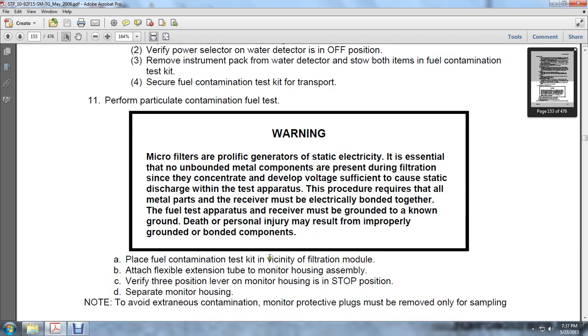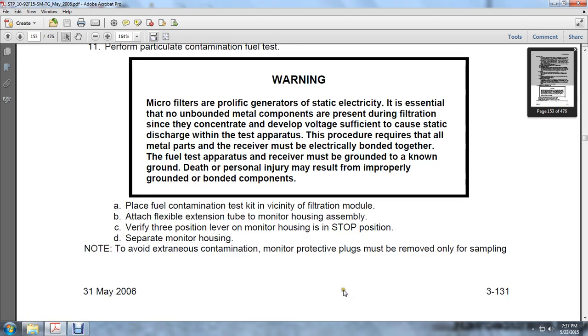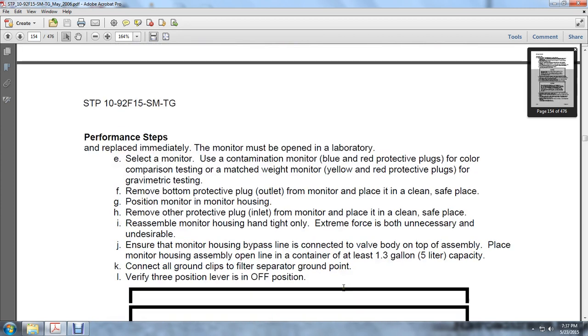Place the fuel contamination test kit in the vicinity of the filtration module. Attach the flexible extension tube to the monitoring housing assembly. Verify the 3-position lever on the monitoring housing is in the stop position. Separate the monitoring housing. To avoid extraneous contamination, monitor protective plugs must be removed only for sampling and replaced immediately. The monitor must be opened in a laboratory.